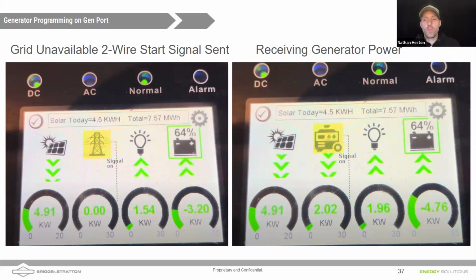On the right, once that generator has been qualified and the signal, the sine wave, is good, it starts using that power. You'll see those green arrows flowing from the generator down into the device, into the Sol-Ark. So it's pulling power out of the generator, coming down in, and then you can see those arrows going up to the battery. When you have negative power on your battery side, it means that the battery's charging. It means it's sending power out to the battery from the Sol-Ark.